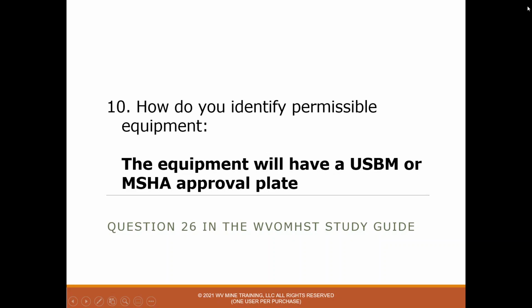10, how do you identify permissible equipment? And the answer is the equipment will have a U.S. Bureau of Mines or MSHA approval plate. So all permissible equipment is identified with an approval plate. So I could come to your mine and you could say, hey, go in the shop and find us a permissible motor. And I could do that by looking at the motors and finding the ones with the tags on them. I would know that if it had that tag, it would be permissible. If it doesn't have the tag, it's not permissible.